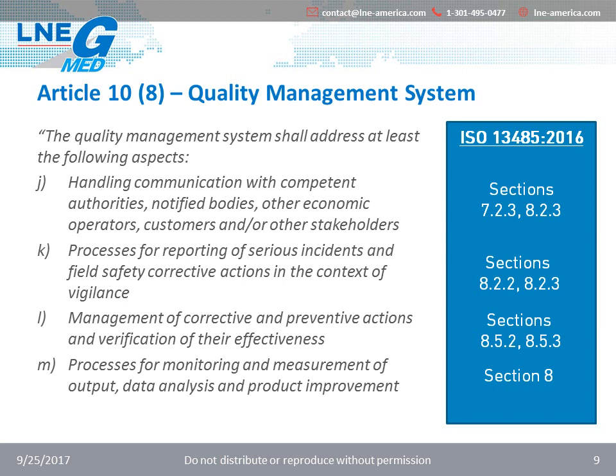So as you can see, a lot of requirements of the regulation related to the QMS are also requirements of the new version of the ISO 13485 standard. So for a lot of you, it might not be affecting the change that you are making now. But be careful, as said earlier, some changes are very specific to the European IVD regulation. So these elements would have to be taken into account.